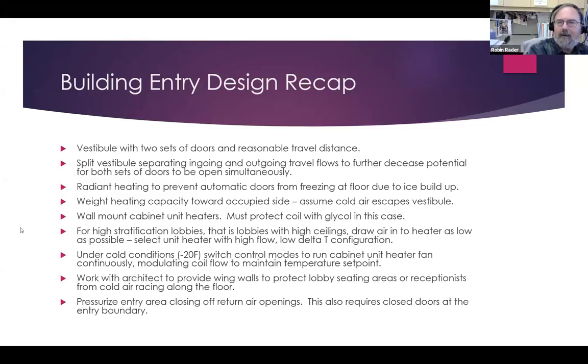Weight heating capacity towards the occupied side. Assume cold air escapes the vestibule. Wall mount cabinet unit heaters. If you do though, you've got to protect them with glycol. For high stratification lobbies, that is lobbies with high ceilings, draw the air into a heater as low as possible. Select the heater with high flow, low delta T configuration. Under cold conditions, that is -20, switch control modes to run the cabinet unit heater fan continuously and modulate the coil flow to maintain temperature set point. So on important vestibules, put a modulating control valve on the coil and switch control modes when it gets cold.